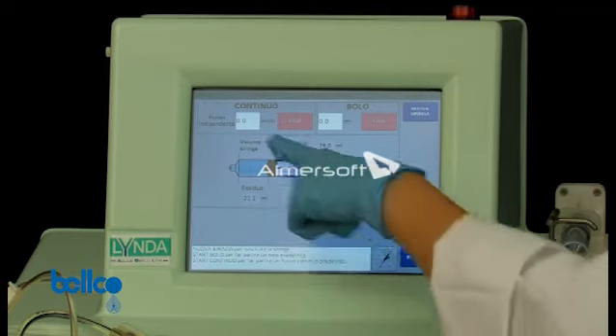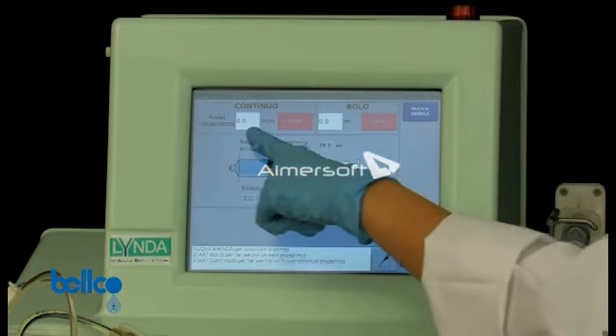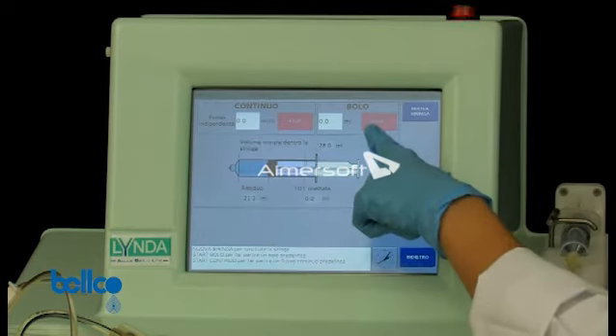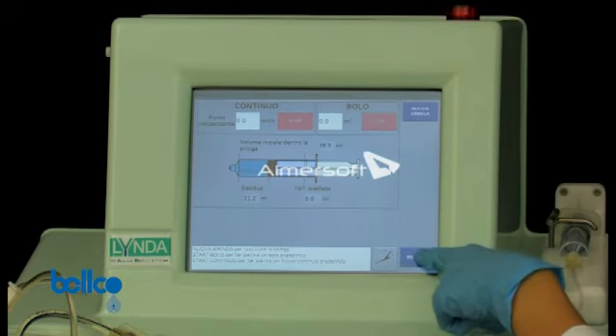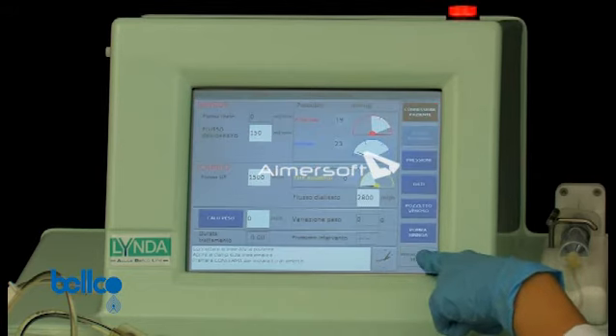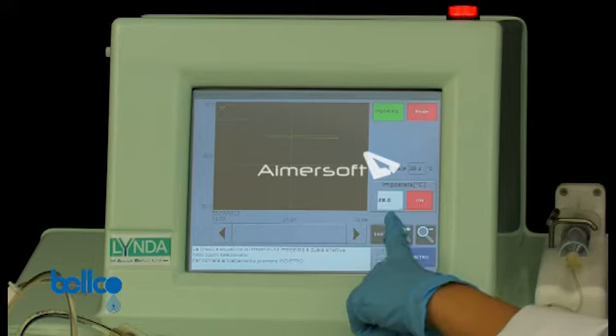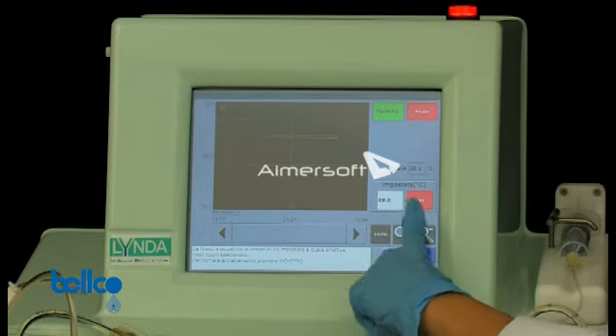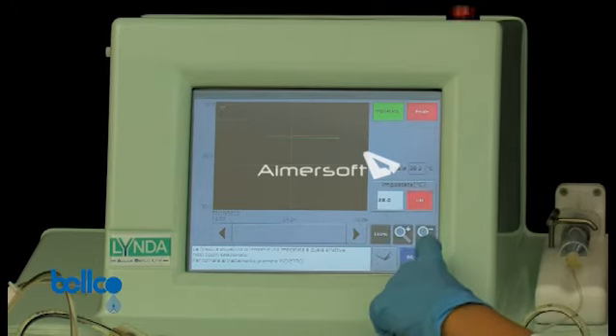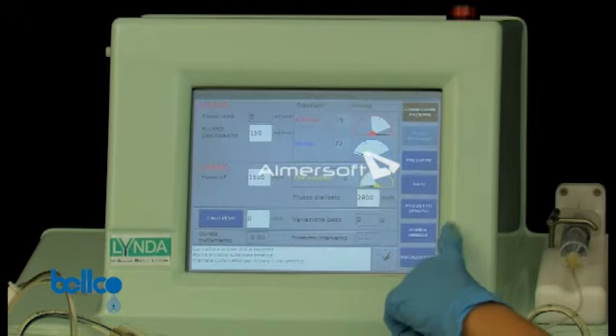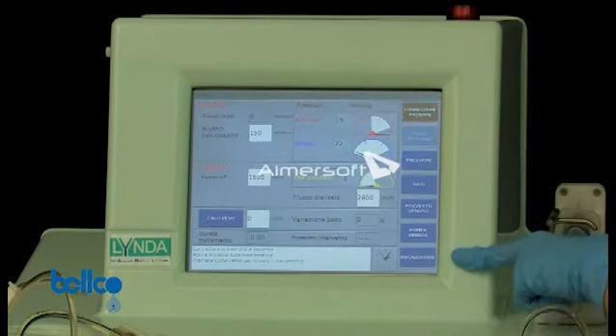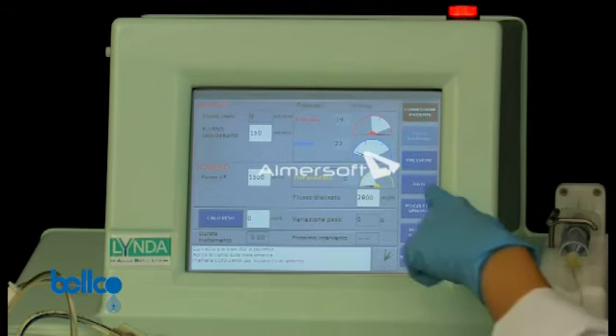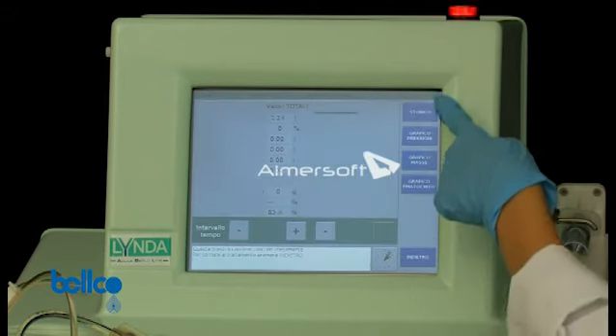The syringe pump button allows changing the amount of solution continuously infused or continuing in bolus mode. Tapping the heater button, you can change the temperature of the heater plate up to a maximum of 40 centigrade. The on-off button allows turning the heater on or off. The data function allows viewing the pressure, weight, and hematocrit meter graph.